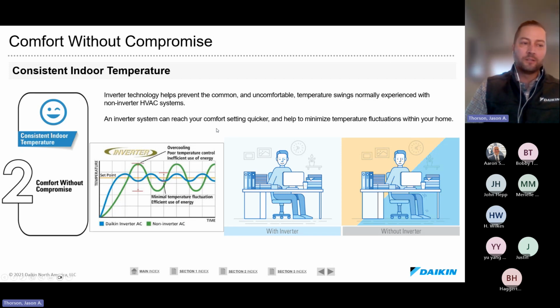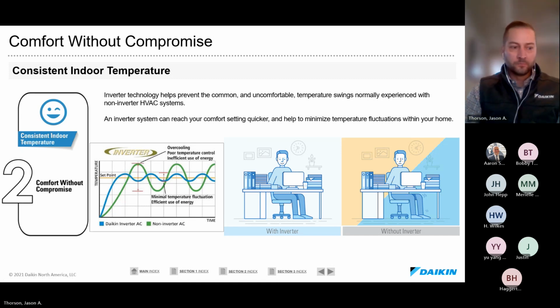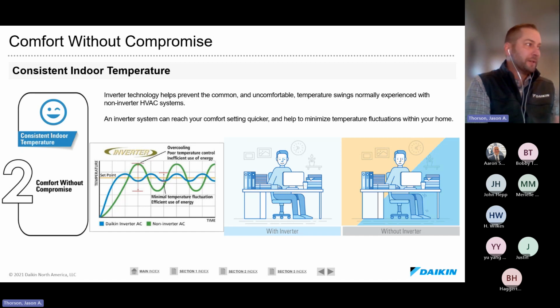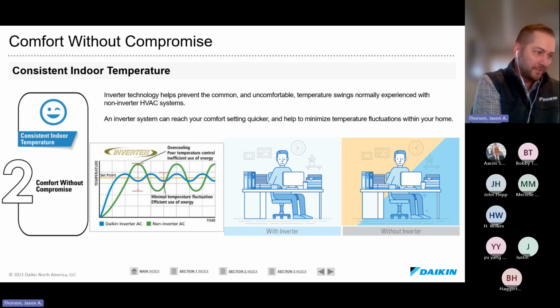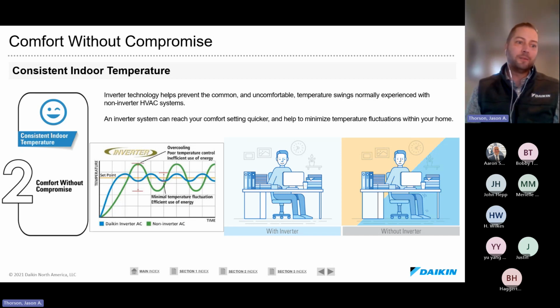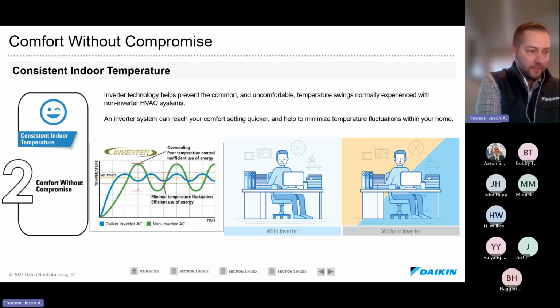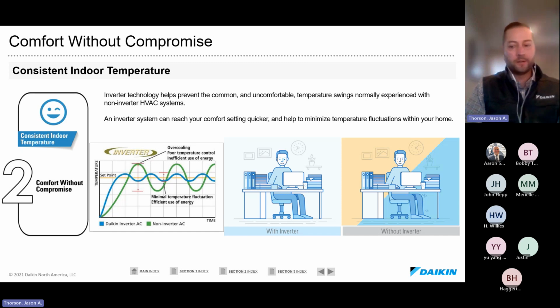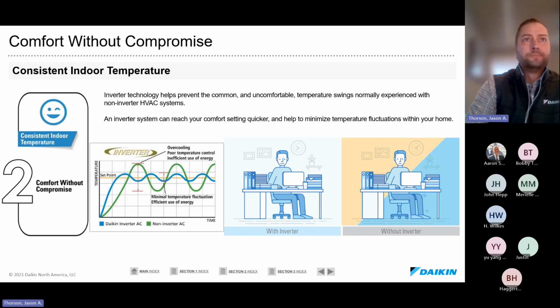We have mini splits that ramp down to the equivalent of an 8-watt light bulb once they hit the set point, truly dialed in, still drawing in air, pulling it through the filter, and if humidity is a concern, still pulling air over the coil, removing moisture, and redistributing it back into the space. What you avoid is hot and cold spots, on-off cycling, like in the house I'm sitting in now. My wife, who's more educated on it now, used to say you freeze out the downstairs to get the upstairs comfortable. You'd sit on the couch, and in summer you'd hear that fan kick on and blow a gush of cold air. With a system that isn't truly variable speed inverter, it's a constant game of compensation to get it where it needs to be, plus needing sleeping spaces colder than downstairs, and so on.